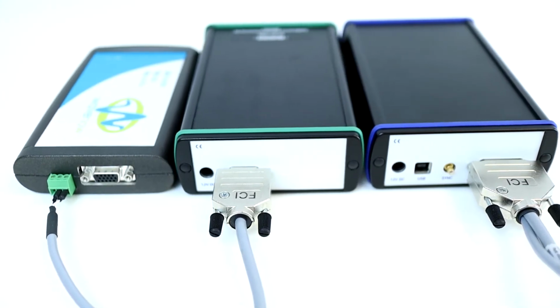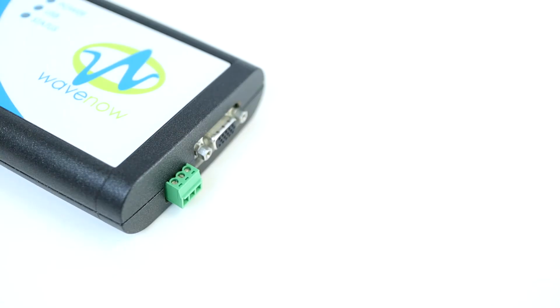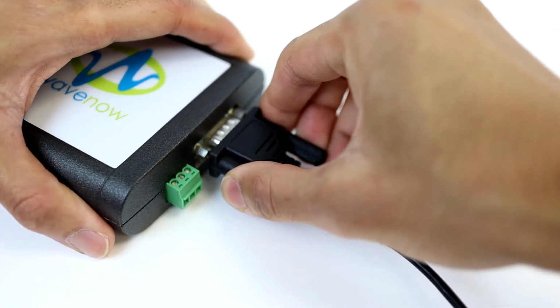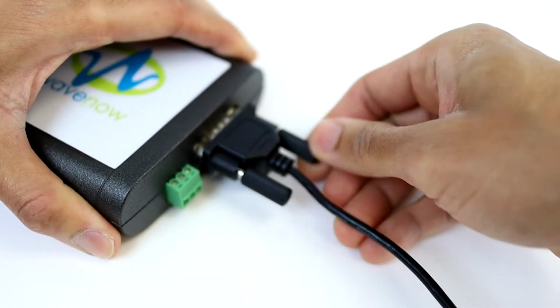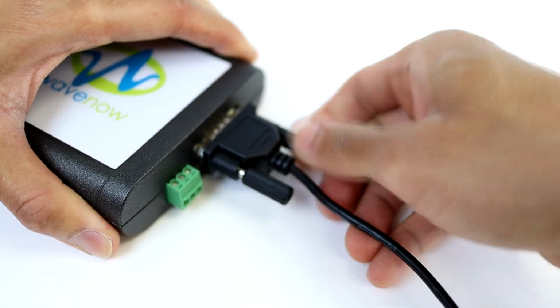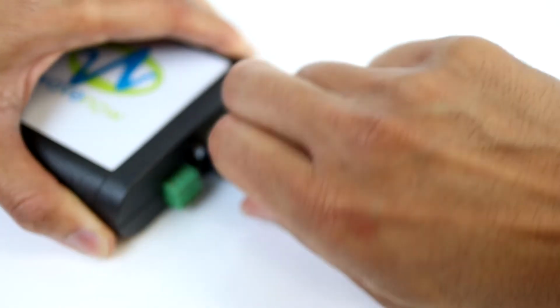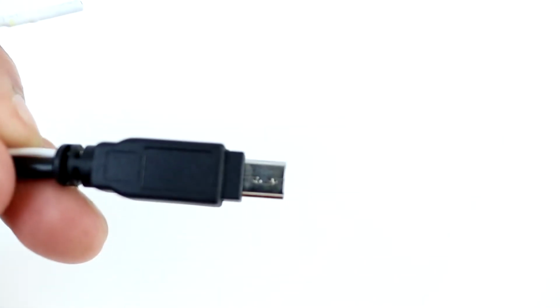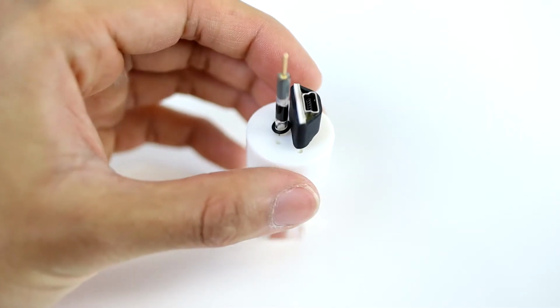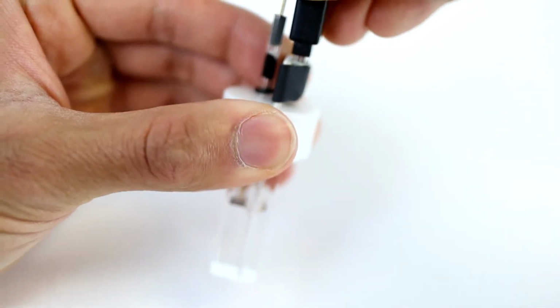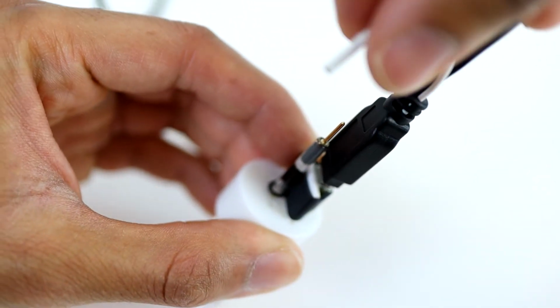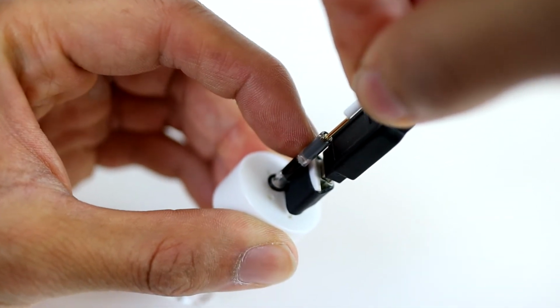Now, the last step is to connect everything together. First, we want to connect the potentiostat to the honeycomb electrode. To do this, plug in the cell cable into the potentiostat. The cell cable is terminated with a mini USB style connector and a white breakout reference port for the reference electrode. Plug in the mini USB into the honeycomb electrode and then connect the white breakout lead into the reference electrode.